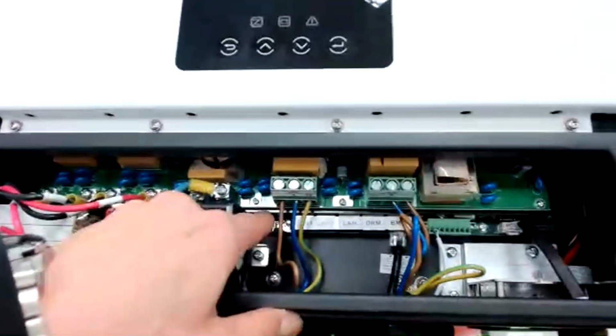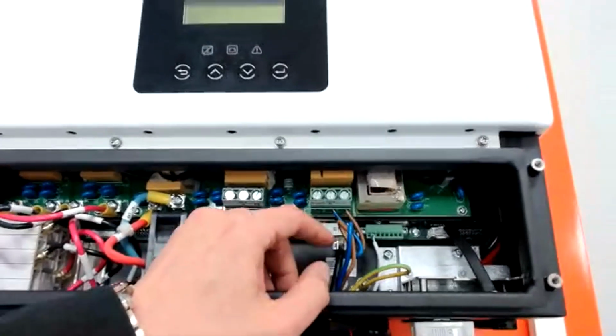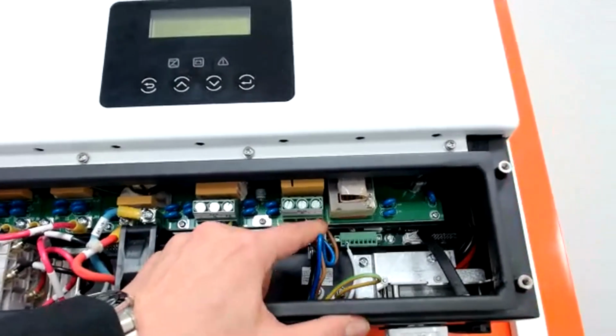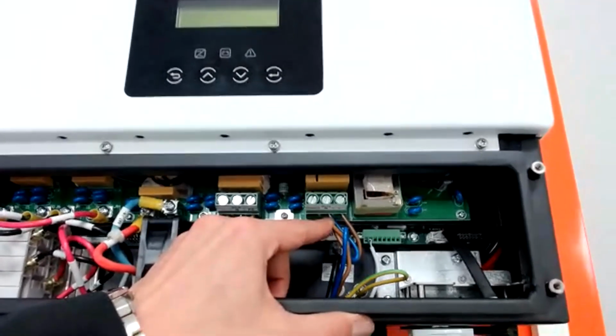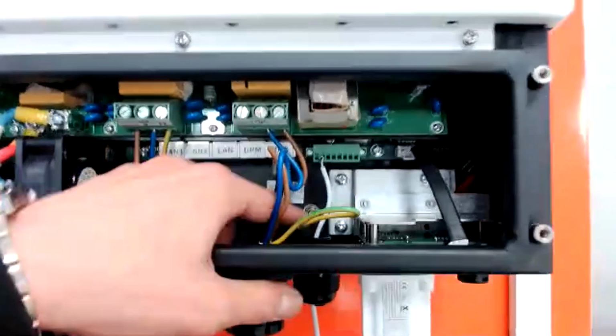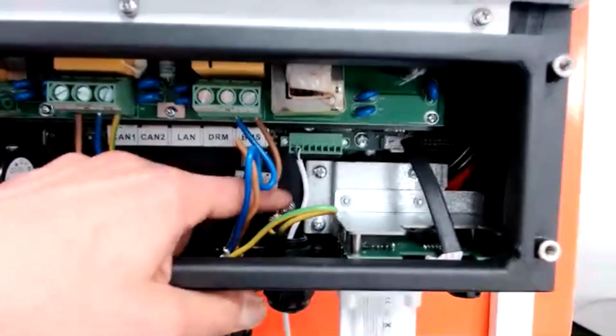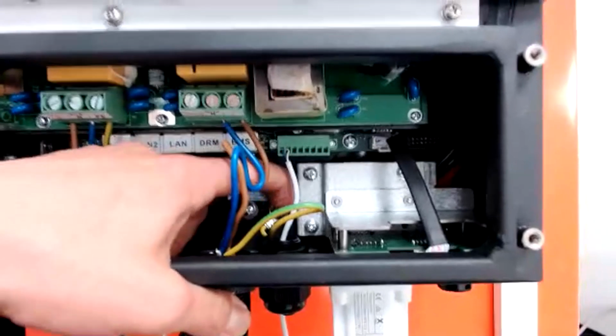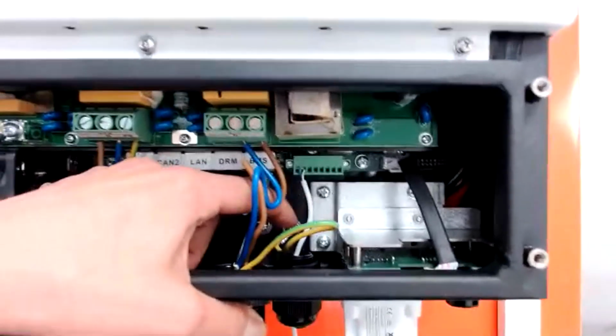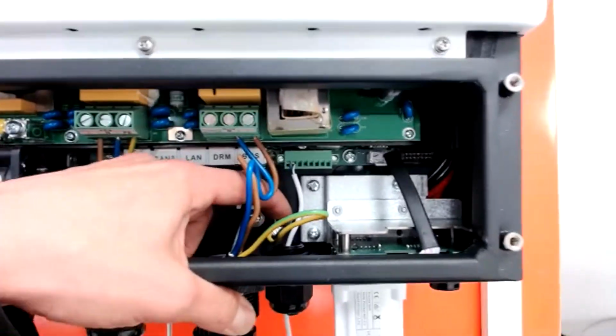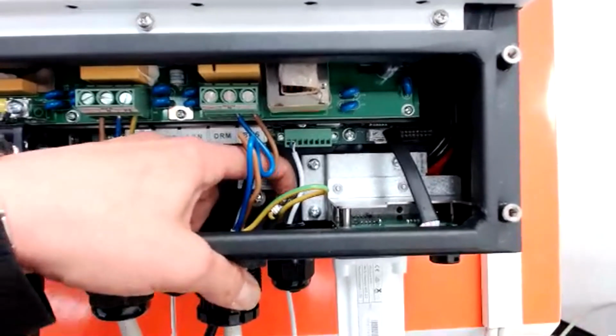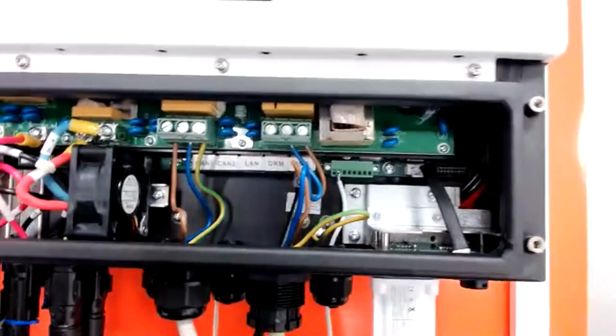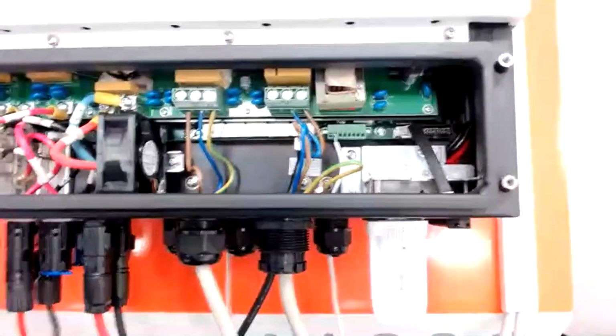You can connect everything to the clamp in the EPS. The grid clamp is a little bit different. There you have just the phase and the neutral cable, and the PE has to be put on the back of the inverter to the chassis. So there is no danger of touching, and no danger of getting an electrical shock by touching it.